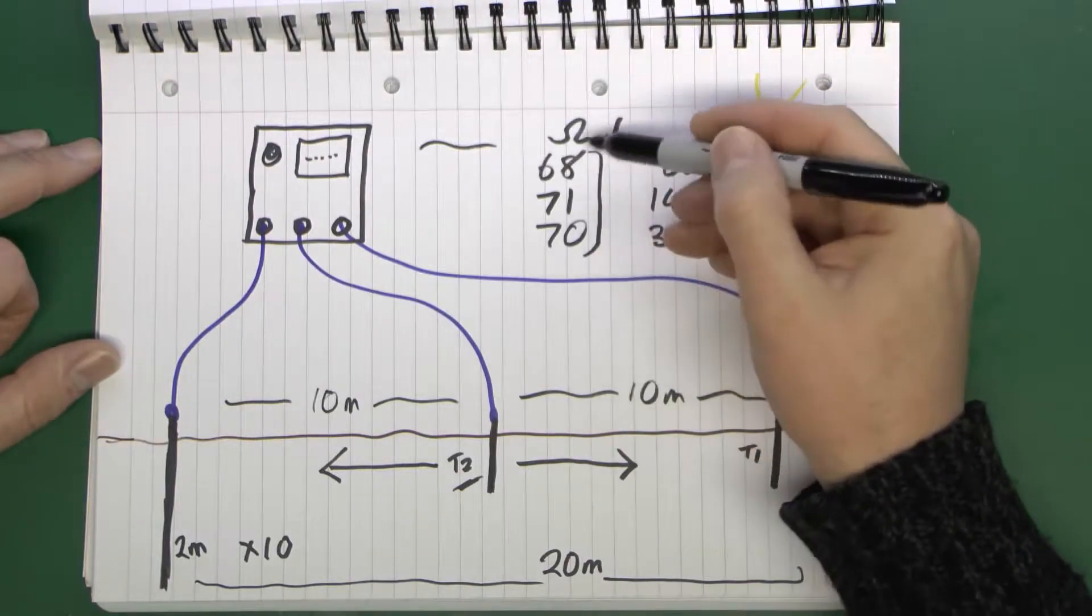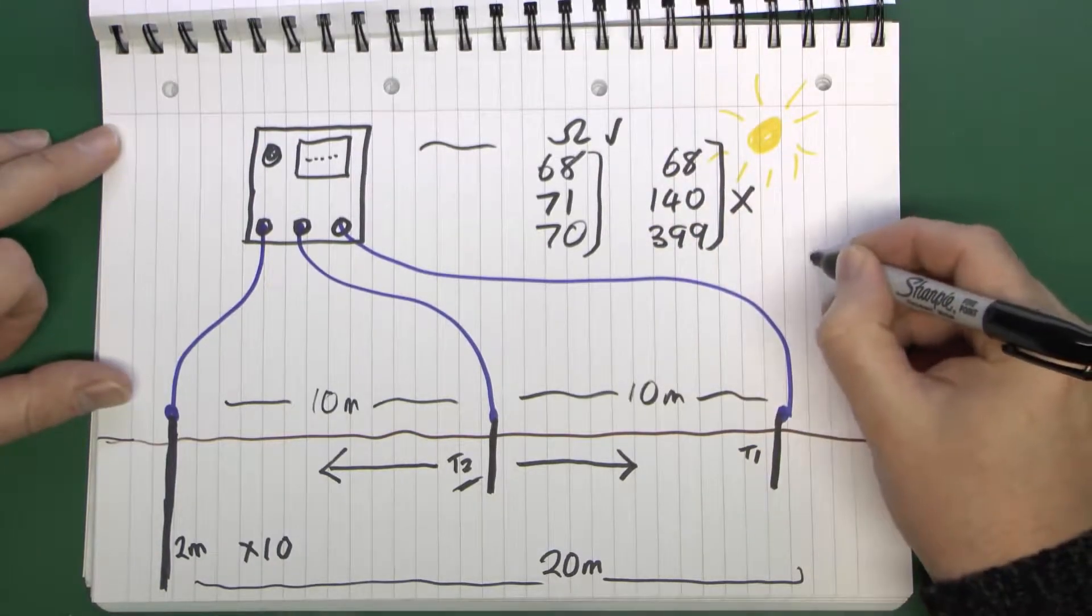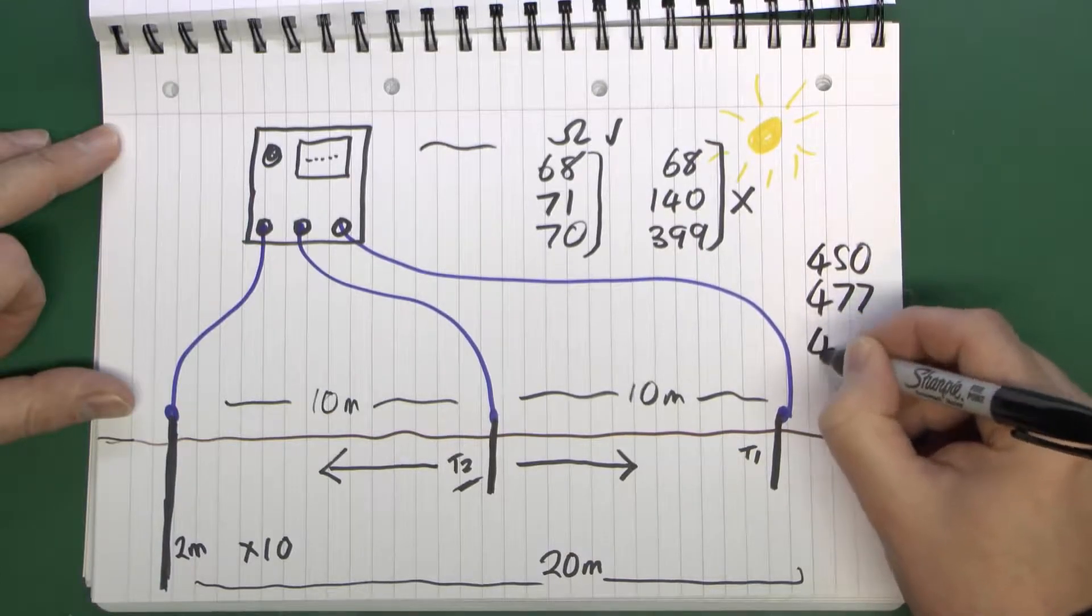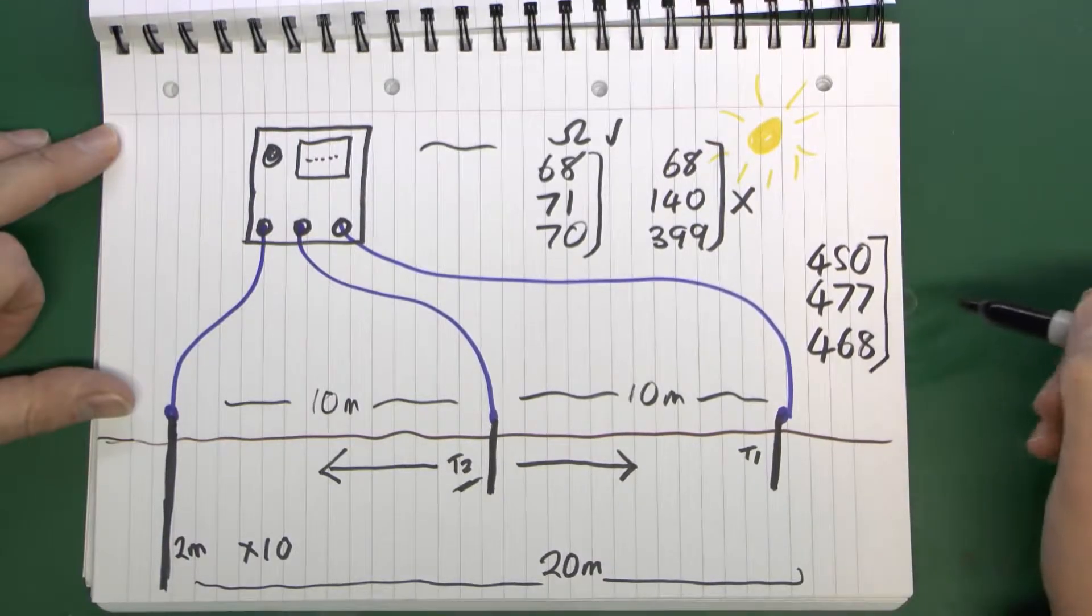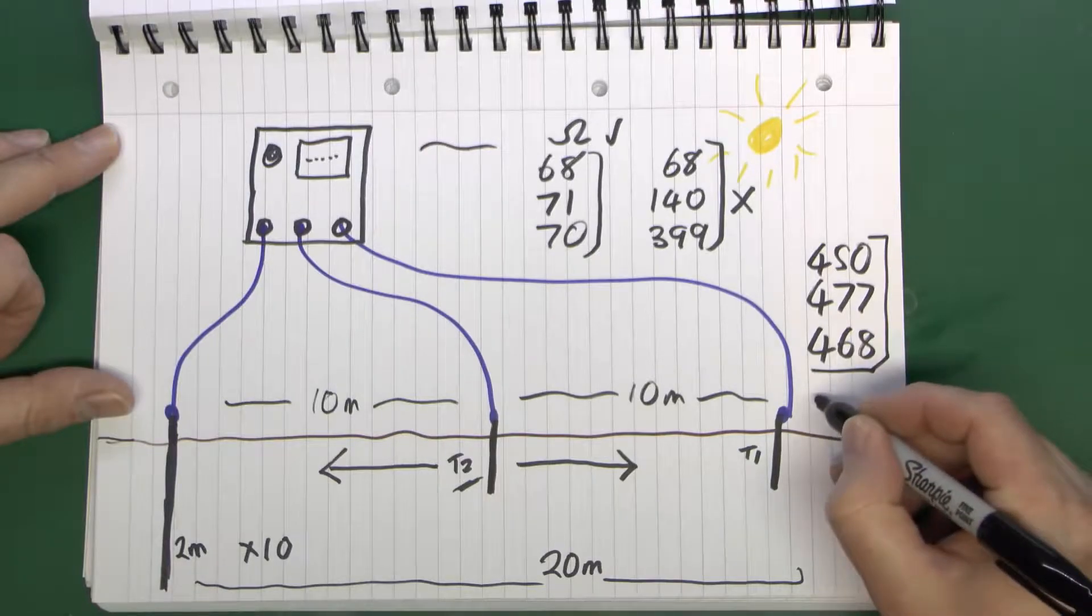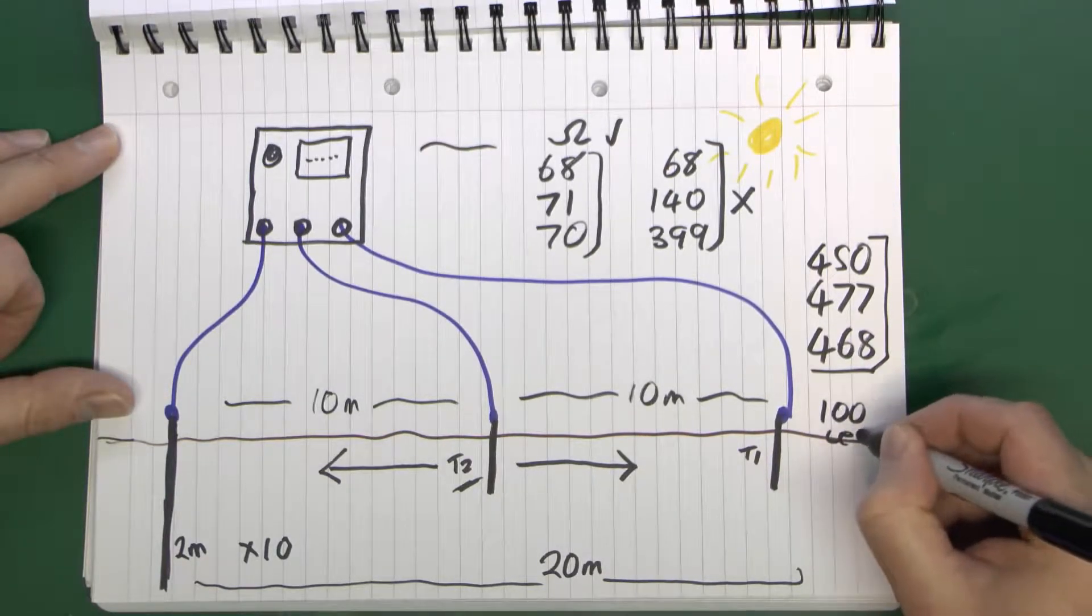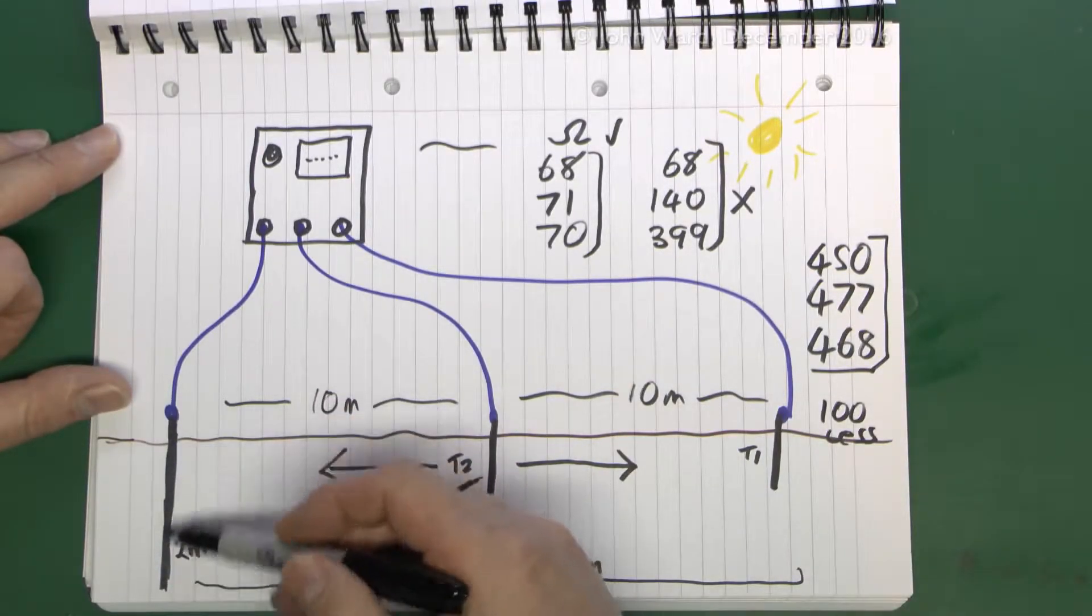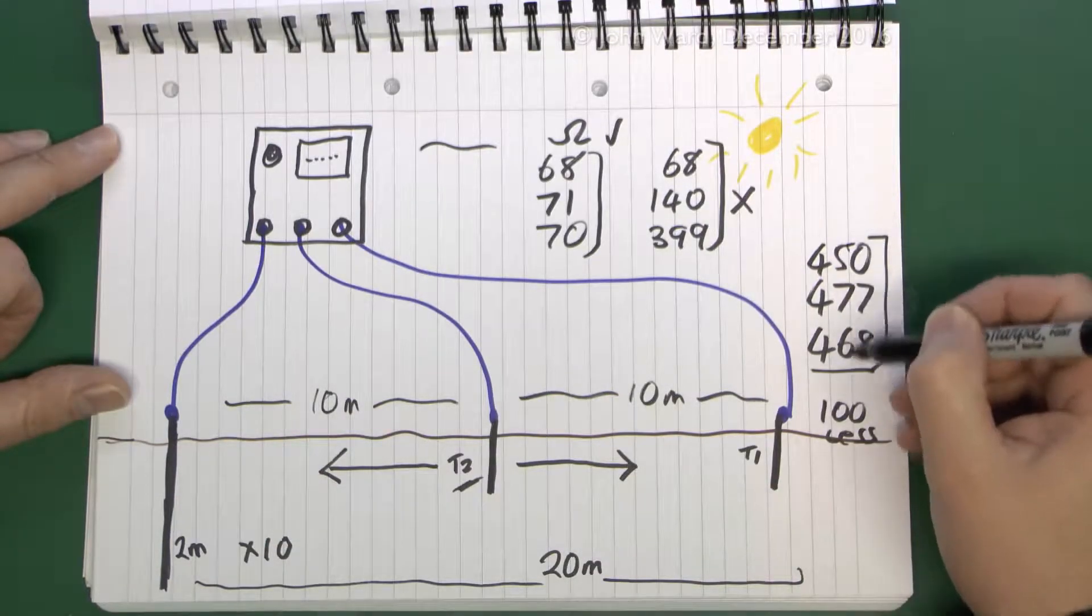Now a final point here: if you get three that are the same but they're all far too high, so say for example you've got three readings that came out as 450, 477, and 468, well yes they're all reasonably close together, but the average of those is in the middle of the 400s range. That is far too high because what you want to find is something in the range of 100 or less. This means that the actual electrode itself which you put in here is not sufficient, so you're going to have to do something about it to reduce this value considerably.